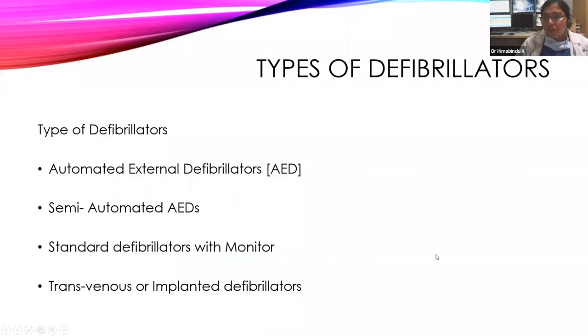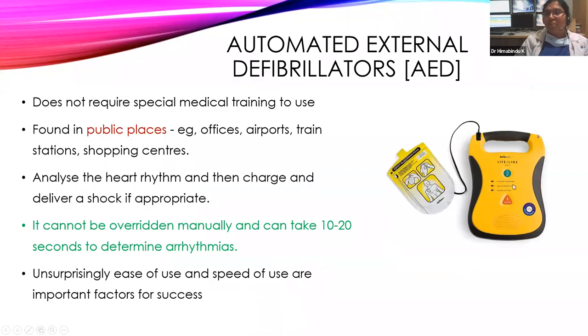Types of defibrillators: automated external defibrillator (AED), semi-automated AED, standard defibrillator with monitor, and transvenous or implanted defibrillator. The AED, seen in public places like airports, railway stations, and shopping malls, automatically detects arrhythmia, charges, and delivers shock — even a layperson can use it. It cannot be overridden manually and takes 10–20 seconds to analyze the rhythm.